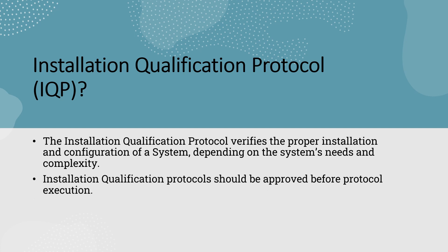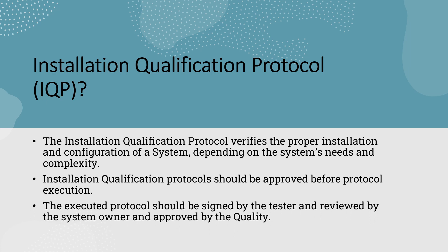The installation qualification protocol should be approved before the protocol execution. It should be approved by the quality, and then only the test can be performed. The executed protocol should be signed by the tester — that is, who has executed the test — and reviewed by the system owner, which means the user department head, and finally approved by the quality.